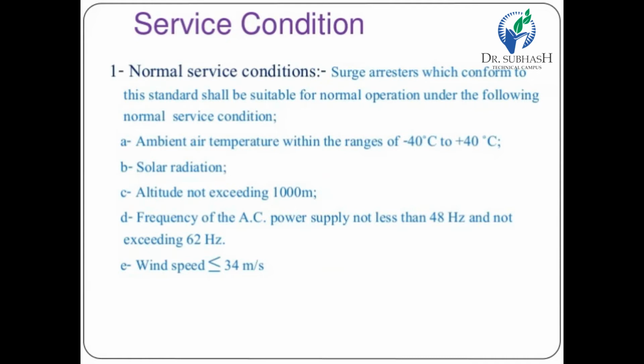Now service condition. Normal service conditions. Surge arrestors which conform to this standard shall be suitable for normal operation under the following normal service conditions. One is ambient temperature within the range of -40 degrees centigrade to +40 degrees centigrade. So this is the range for normal service conditions.